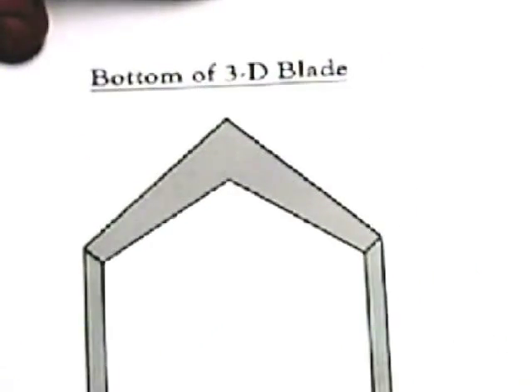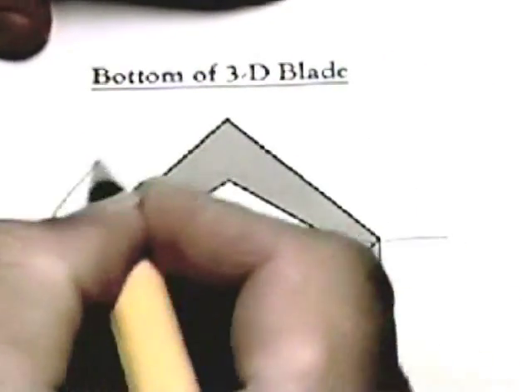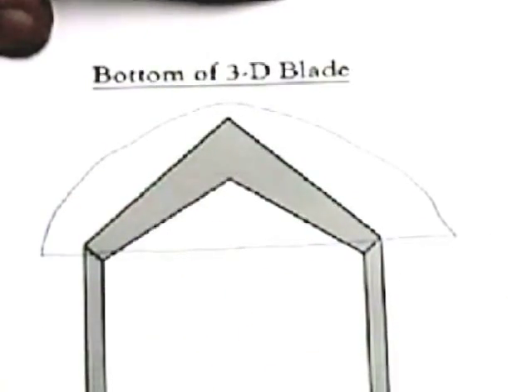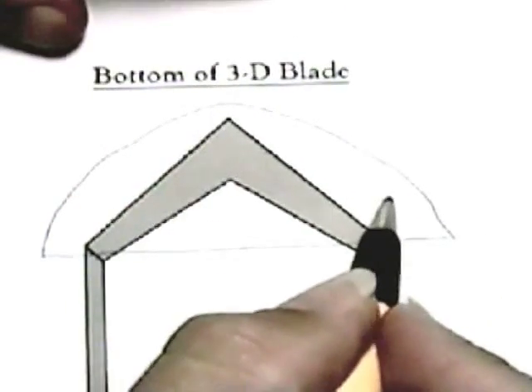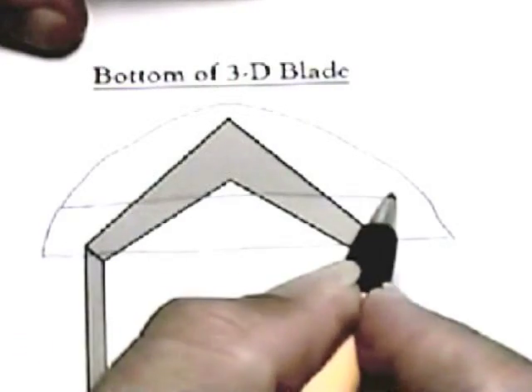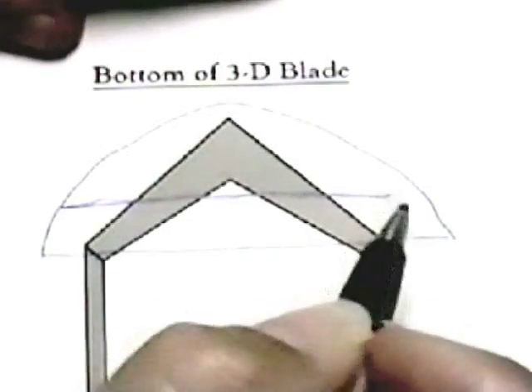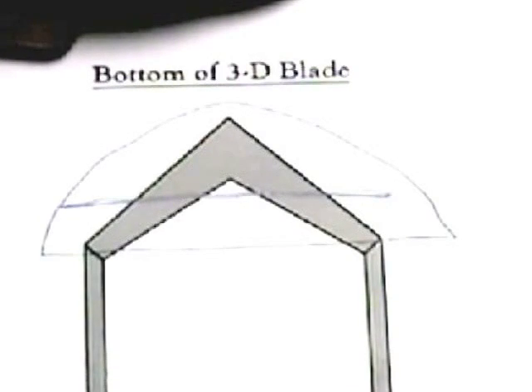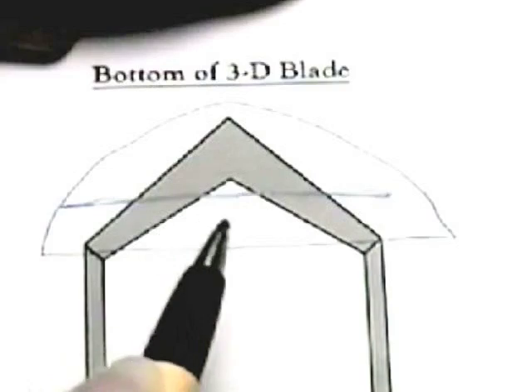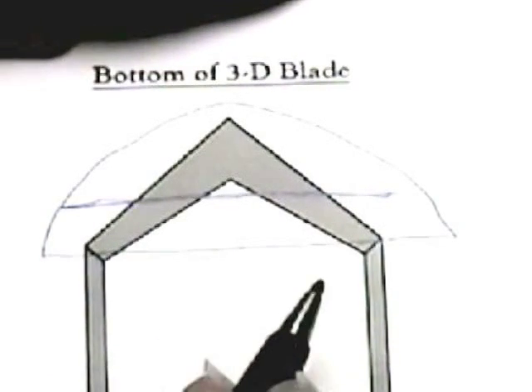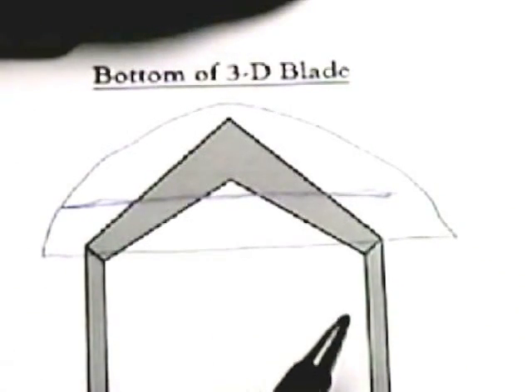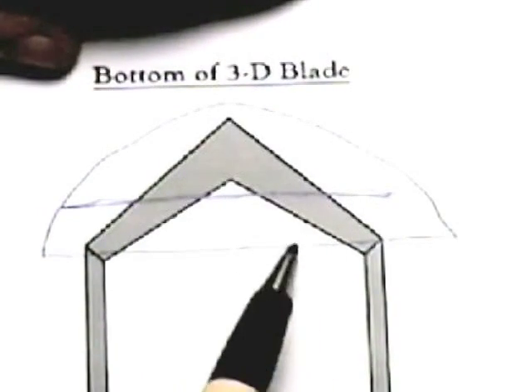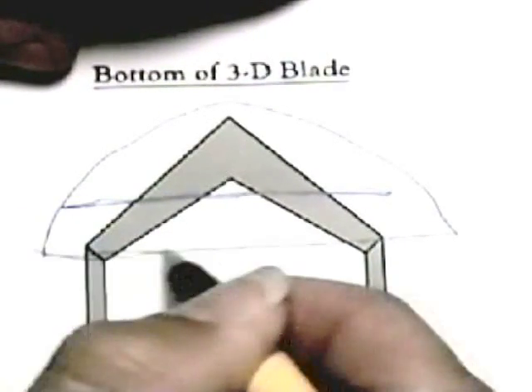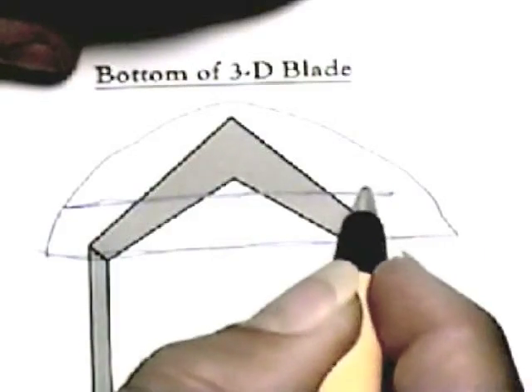This is a trapezoidal blade when you look at this portion of it. So I would recommend advancing this blade only up to this point if a surgeon is using a smaller phaco-tip and having trouble with BSS leakage. And then after the lens is emulsified and IA is performed, I would reinsert the blade all the way through and insert it past the shoulders to gain the full effect of these bevels.